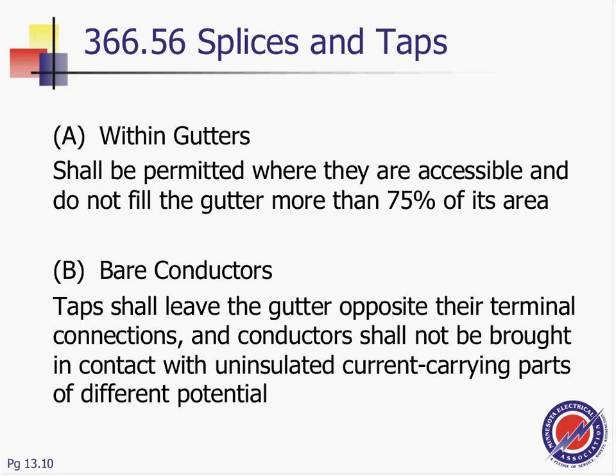In the gutters, if I'm doing splices and taps, I can't fill more than 75%. If I have bare conductor, taps shall leave the gutter opposite their terminal connection, and the conductor shall not be brought in contact with uninsulated current-carrying parts of a different potential. So that you have separation. If you have different voltages, all the conductors are rated for 600 volts, but if you have 600 volts, 480, 277, 208, 120, make sure they're not touching each other. Insulated ones can touch, but if they're bare conductors or bare bars, you're going to short them. Any questions about that?